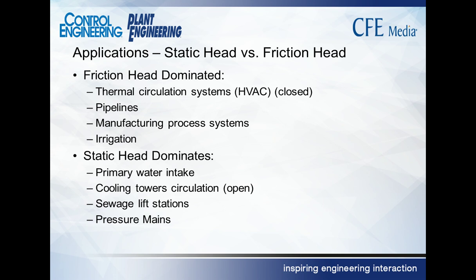Pipelines tend to be mostly friction. The Keystone pipeline pumps downhill. If you hooked it up to a tank on the top and you opened up the bottom, it actually would have some liquid coming out of it, not very much, so they use pumps to speed that flow up. The pumps primarily overcome the friction through the pipeline. A lot of your manufacturing processes do very little elevation change and are mostly because of all the piping it takes to get the liquid, to get the beer from the brewery over to the chiller. It's the length of that pipe that they're overcoming. Irrigation is a case where there's typically a lot of friction. You may not be lifting the water very far, but you're running it through sprinkler heads or whatever. So there's a lot of friction.